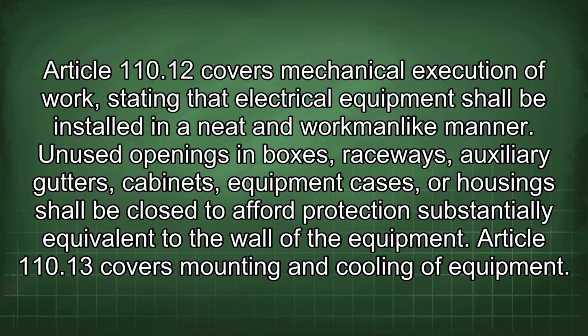Article 110.12 covers mechanical execution of work, stating that electrical equipment shall be installed in a neat and workmanlike manner. Unused openings in boxes, raceways, auxiliary gutters, cabinets, equipment cases, or housing shall be closed to afford protection substantially equivalent to the wall of the equipment. Article 110.13 covers mounting and cooling of equipment.